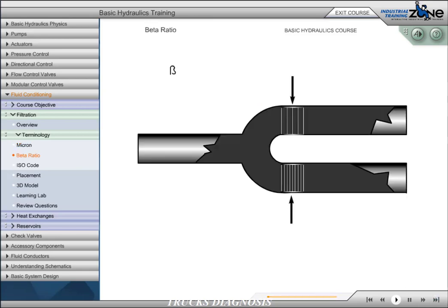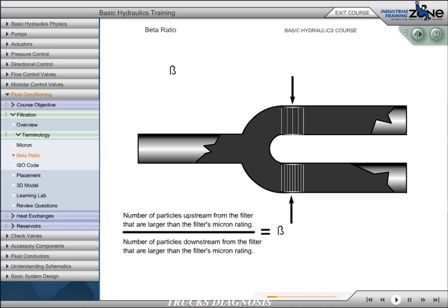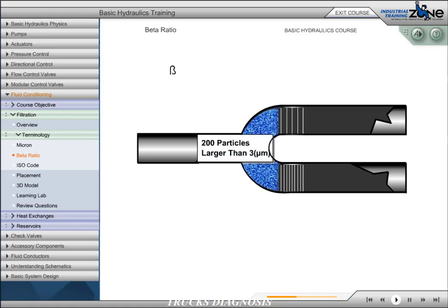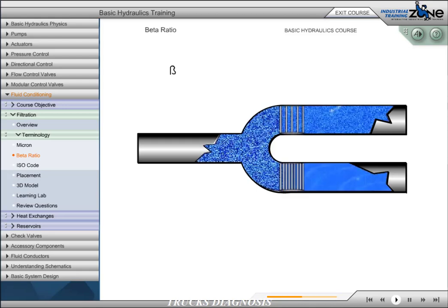Filtration devices are used to filter particles out of the system's fluid. A filter's efficiency is rated with a beta ratio. The beta ratio is the number of particles upstream from the filter that are larger than the filter's micron rating, divided by the number of particles downstream larger than the filter's micron rating. A filter that allows more particles through — one that is less efficient — has a low beta ratio.